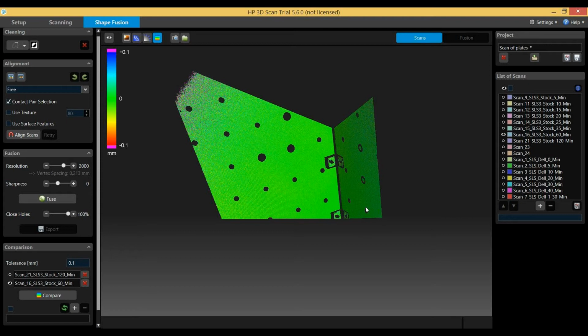Heating up means, let's say, put the camera on the laptop, switch on the projector, and use not the black image, because that will create a different thermal situation in the projector. Use some test picture with a pattern and leave it like this for 30-35 minutes, just without doing anything.